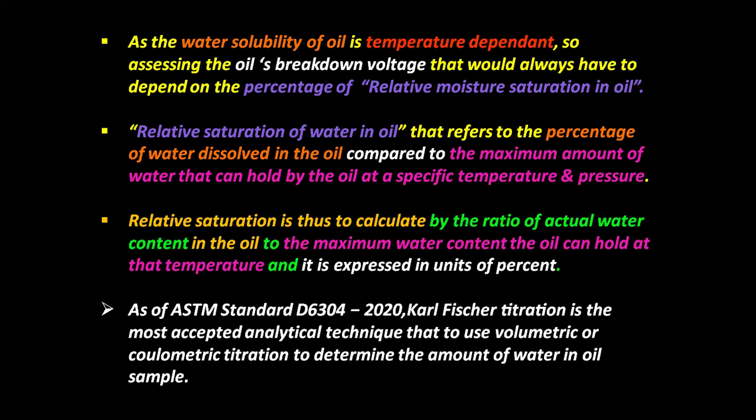As per ASTM standard D6304-2020, Karl Fischer titration is the most accepted analytical technique, using volumetric and coulometric titration to determine the amount of water in an oil sample.